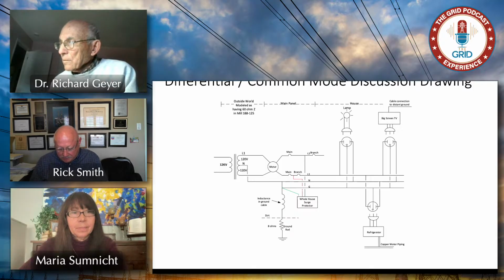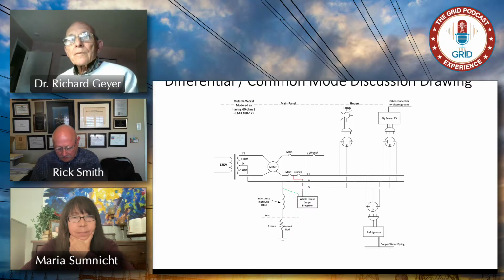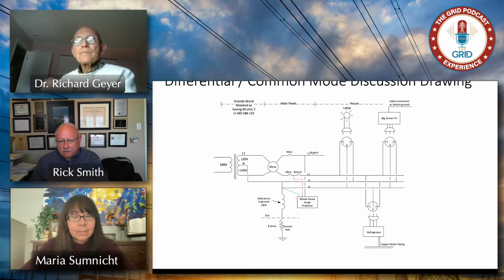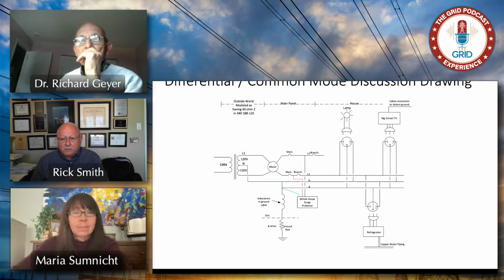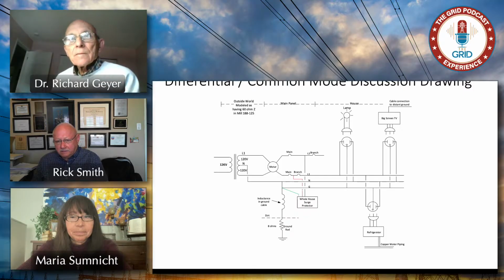Now when you come to something like your refrigerator, if you're not an E1 buff, you might have used copper pipe to tie in the water line, right? So now you've got an issue, because whatever voltage exists between the three wires and ground, with respect to ground, is going to drive current out inadvertently, not where it's supposed to go, but back out through the copper line supplying your refrigerator. That's a problem. Similar problem with your big screen TV: if you've got an external cable connection, it's referencing a different ground than your main panel ground, so you've got another path for that common mode signal to travel, which is bad.